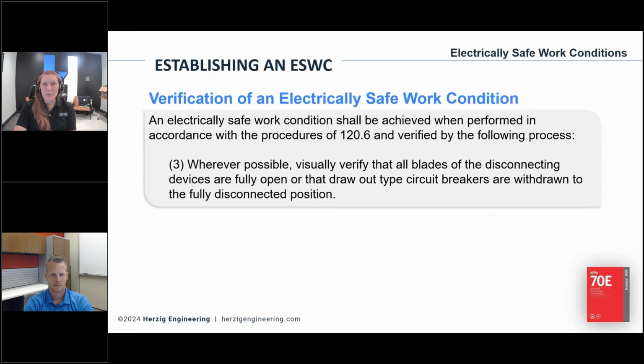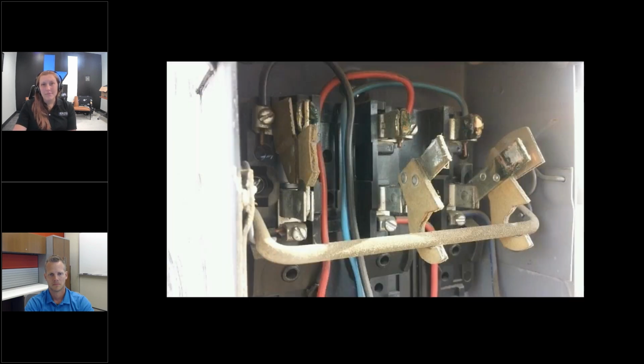Okay, step number 3, moving right along. Wherever possible, visually verify that all blades of the disconnecting device are fully withdrawn or that draw-out type breakers are withdrawn to the fully disconnected position. In other words, if something's broken, we want to know that ahead of time. Right? So if you can, at this point, you do still need to wear PPE because the line side at least is still going to be energized. But if something broke or came loose or the handle isn't even connected to the rest of the bars at that point, I've seen that happen before. Yeah, let's get some eyes on those, see that the blade's disengaged.